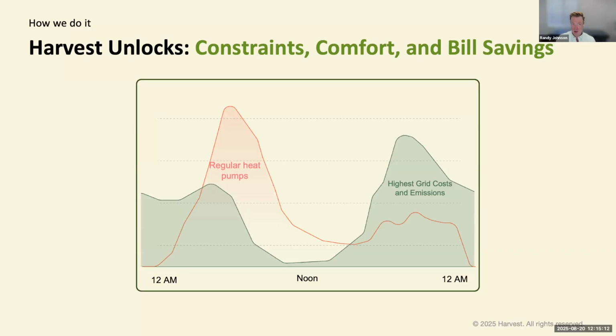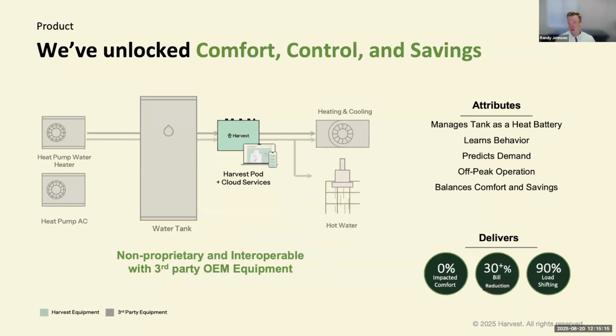Now, the Harvest platform is actually a smart controller. Essentially, we take an off-the-shelf, highly efficient heat pump water heater that creates water very efficiently at about 150 degrees Fahrenheit. It's a CO2 heat pump, called a monoblock, so all the refrigerant is closed in—very low global warming potential refrigerant. That stores water in a thermally insulated and stratified tank, and we use that stored water to deploy both heating and hot water in the home through a hydronic coil, integrated directly into the domestic hot water system.